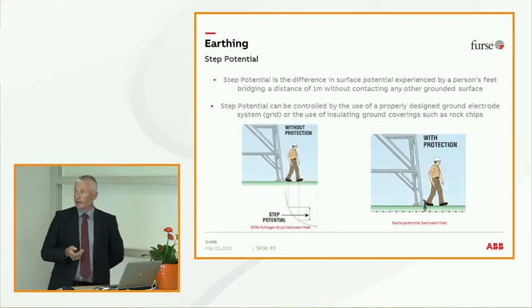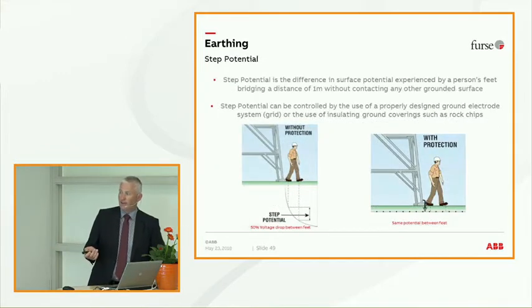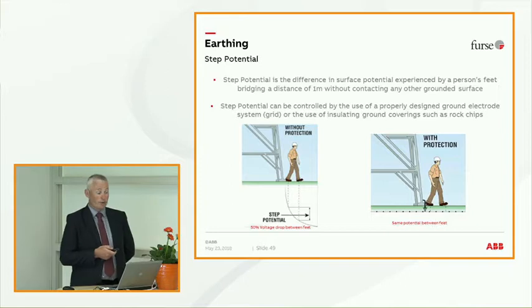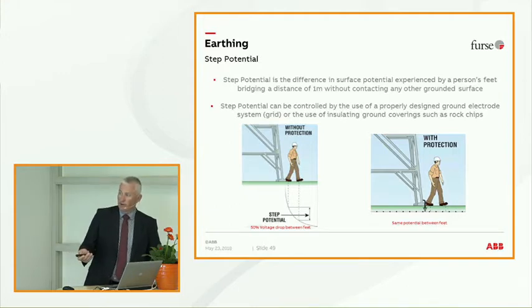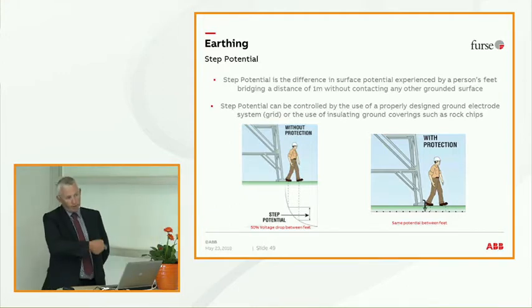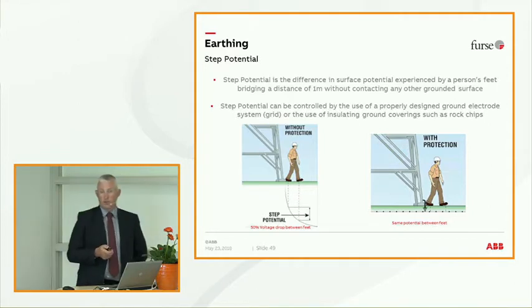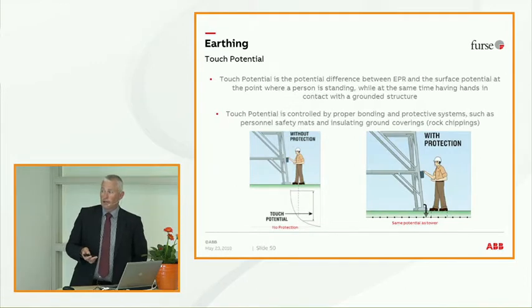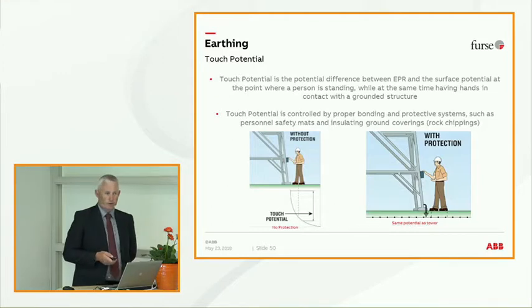Just quickly again, I mentioned the step potential. It's that variance in between. If you put an earthing system in, there's no variance. There's no equipotential difference. This is what kills people. There are standards for livestock, for instance, if it's horses or cattle, because you can imagine if you've got that voltage going across the front legs, it would go through the heart. It would kill them. So it's very critical to bear that in mind. The other one is the touch potential, because it's just going to transfer across. It's not just a step potential.